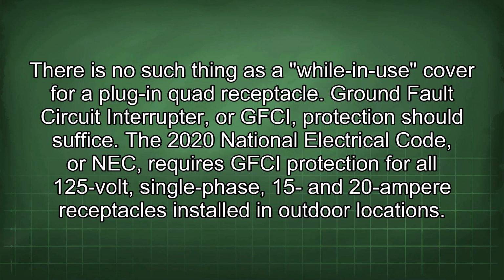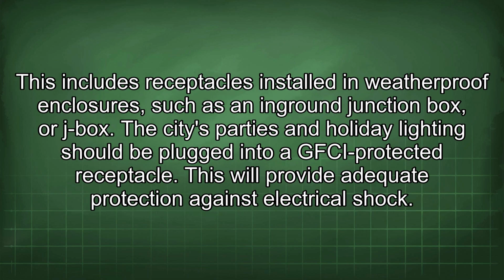There is no such thing as a while-in-use cover for a plug-in quad receptacle. Ground fault circuit interrupter, or GFCI, protection should suffice. The 2020 National Electrical Code, or NEC, requires GFCI protection for all 125-volt, single-phase, 15 and 20 ampere receptacles installed in outdoor locations. This includes receptacles installed in weatherproof enclosures, such as an in-ground junction box, or J-box.